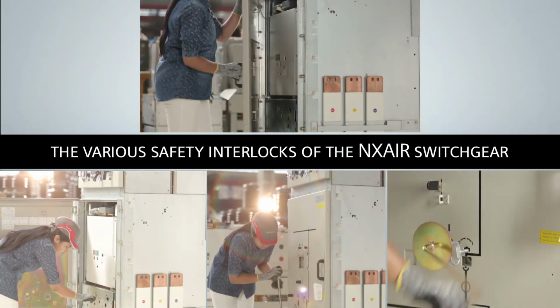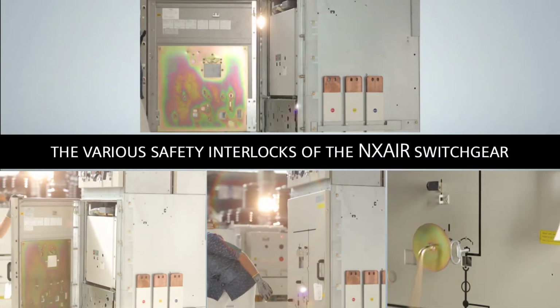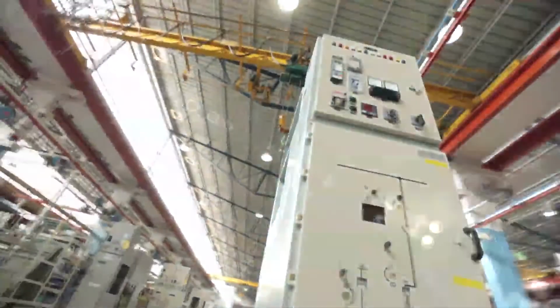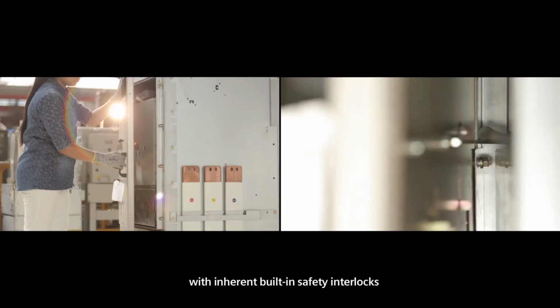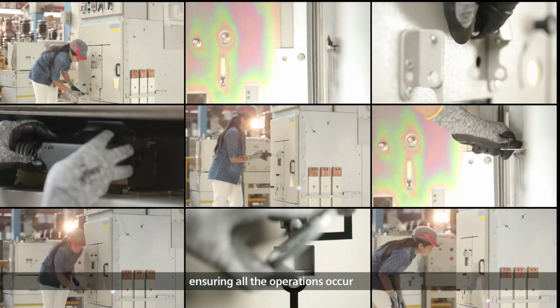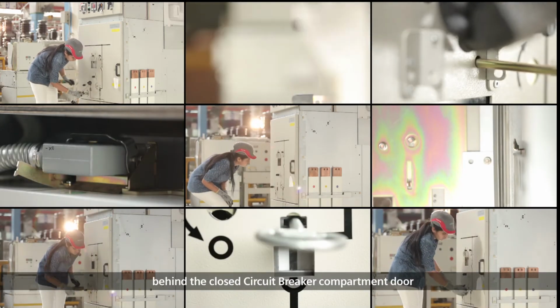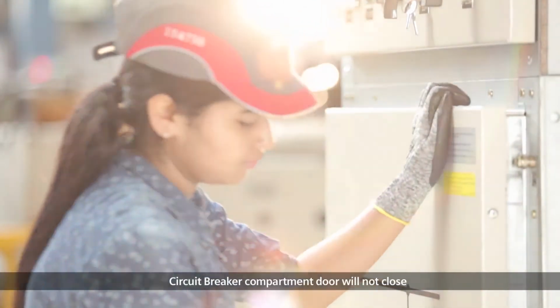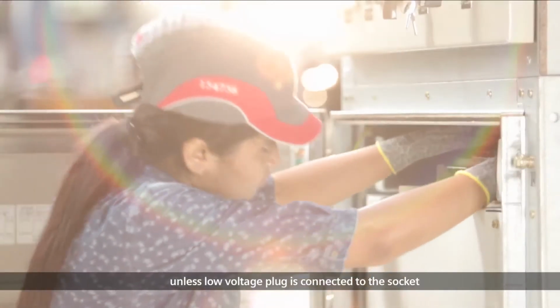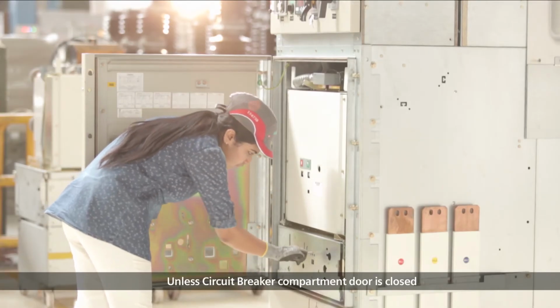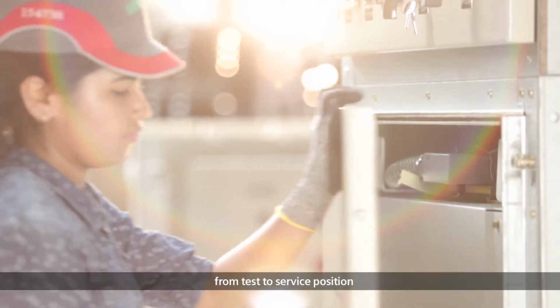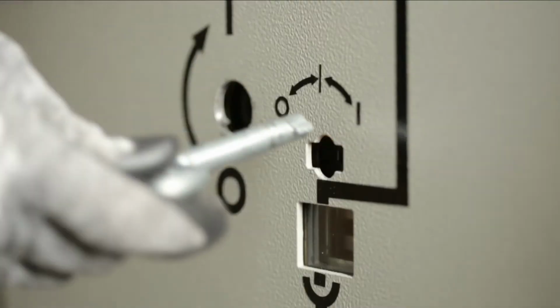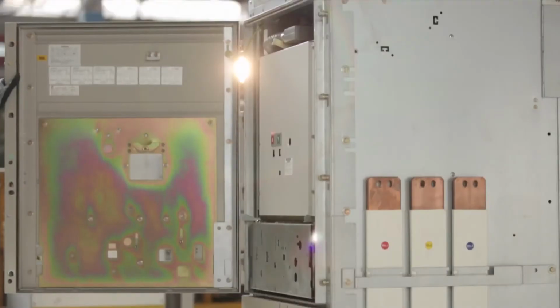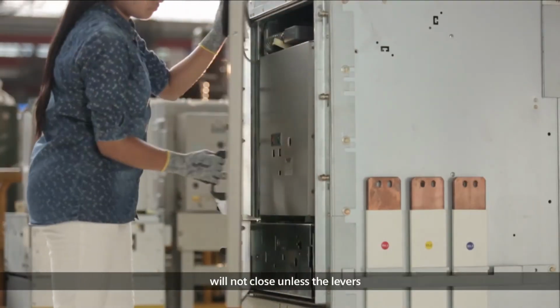Now we will take a look at the various safety interlocks, which are part of the standard features of the NX-Air switchgear. The NX-Air switchgear is provided with inherent built-in safety interlocks, ensuring all the operations occur behind the closed circuit breaker compartment door. Circuit breaker compartment door will not close unless low voltage plug is connected to the socket. Unless circuit breaker compartment door is closed, the circuit breaker cannot be moved from test to service position. Circuit breaker compartment door will not close unless the levers are in locked position inside the panel.